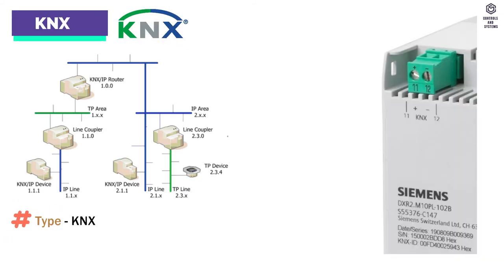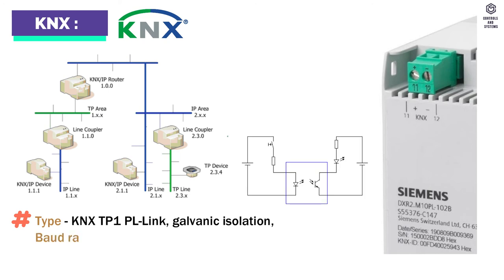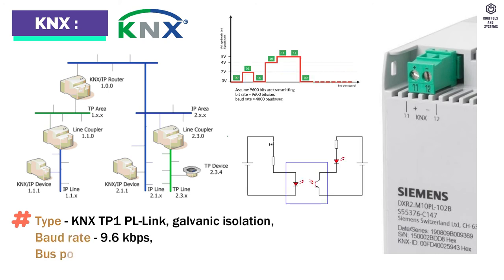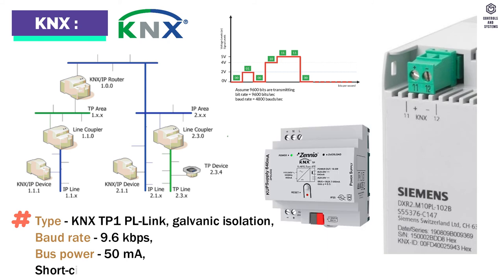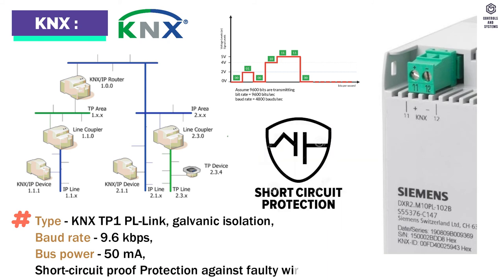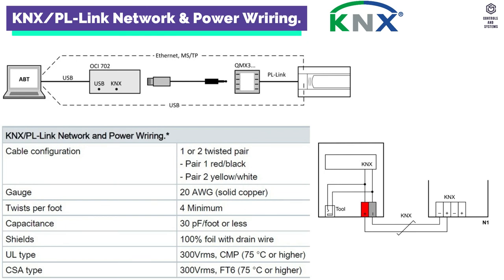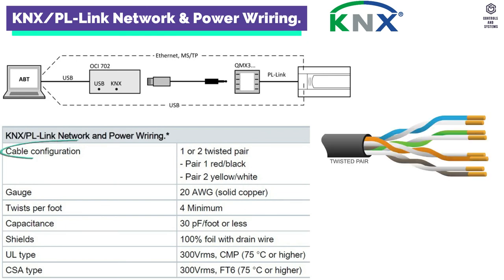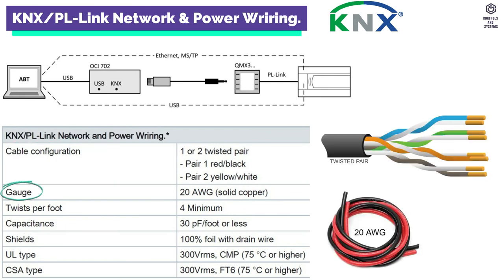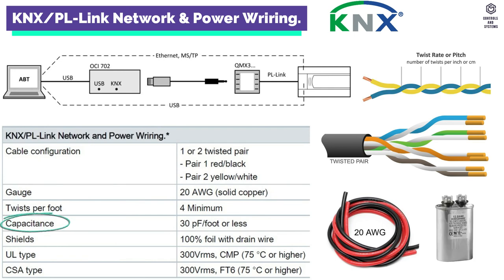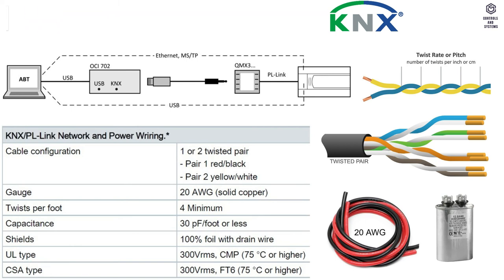KNX: type is KNX TP1 PL link, with galvanic isolation. Baud rate is 9.6 kbps. Bus power is 50 mA. Short-circuit proof protection against faulty wiring at maximum AC 24V. KNX PL link network and power wiring cable configuration gauge, twists per foot, capacitance, shields, UL type, and CSA type are shown in the table.